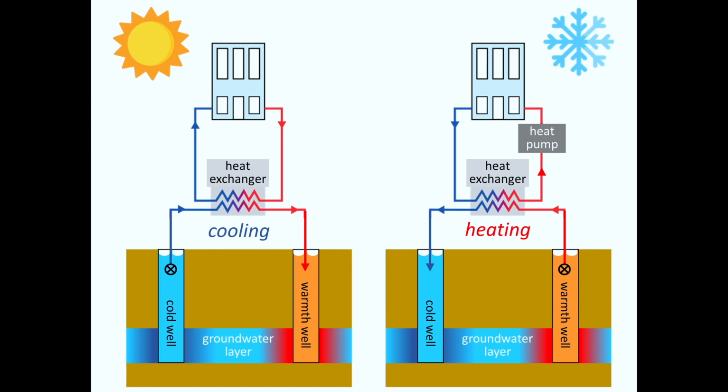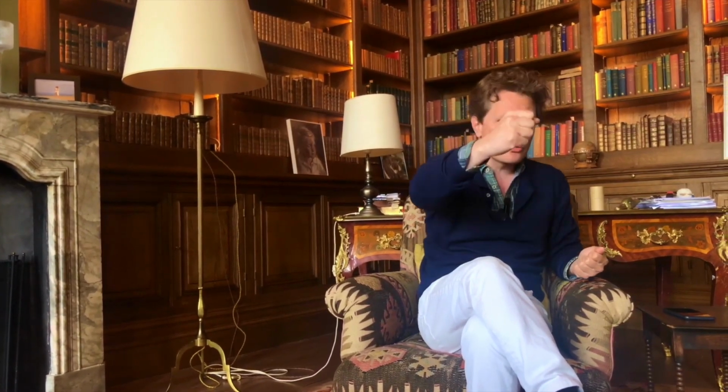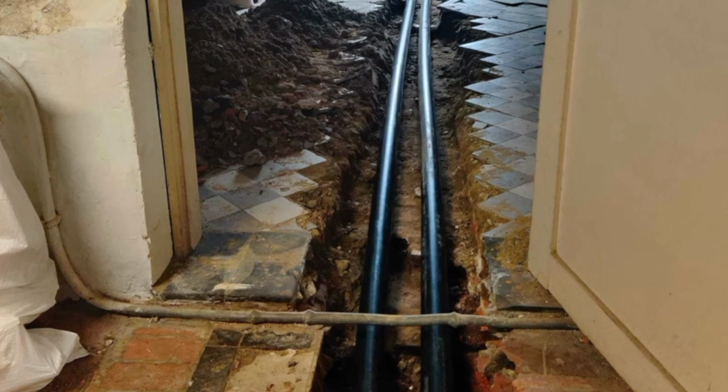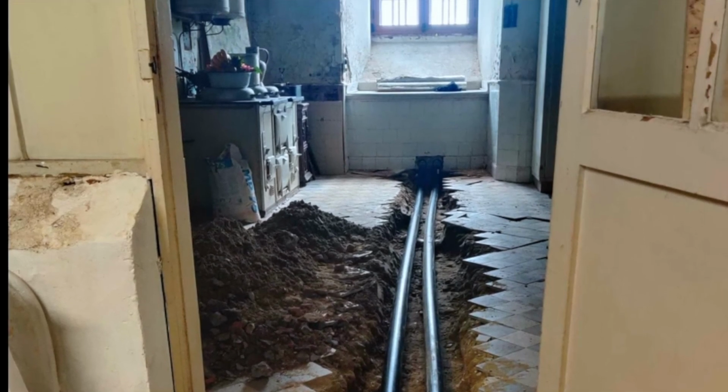And actually, in the real winter, it creates almost enough energy to compensate for the energy that we lose in the heating system of the house. So when the water leaves at 50 degrees in the radiators and comes back at 46, the heat pump creates the 4 degrees that we are losing. And so basically we are using part of the calories in the water, we bring it in the heat pump, it increases the warmth difference and sends it in the heating system of the house. So it works pretty well.